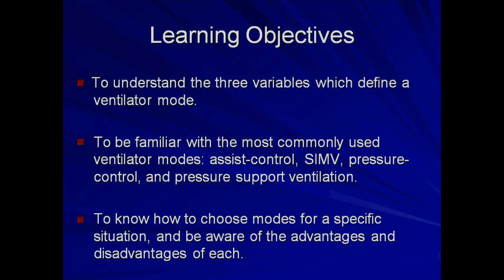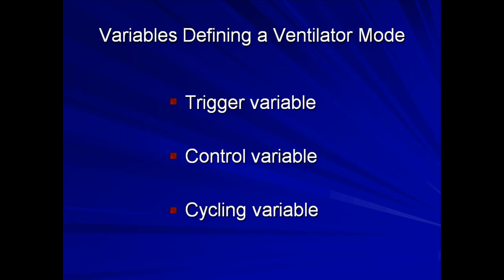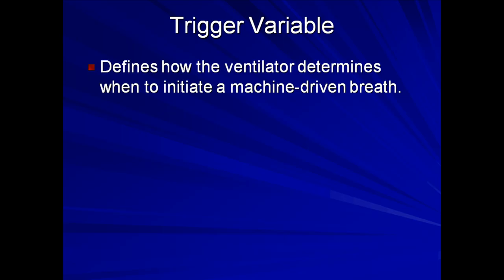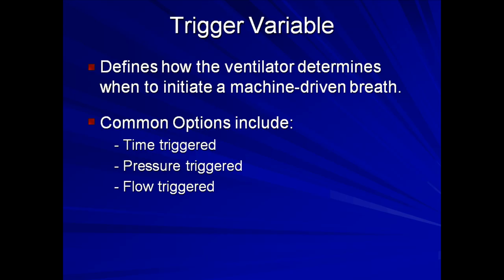Patterns of ventilation, also known as ventilator modes, can be partially defined based on the following three variables: the trigger variable, the control variable, and the cycling variable. The trigger variable defines how the ventilator determines when to initiate a machine driven breath. For patients with no spontaneous respirations, the passage of a specific duration of time is a trigger for a breath.